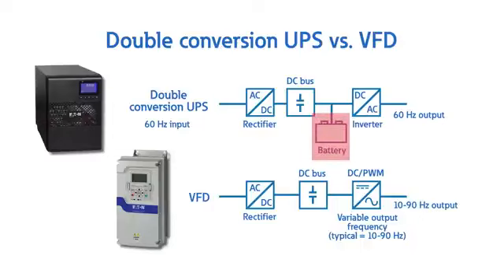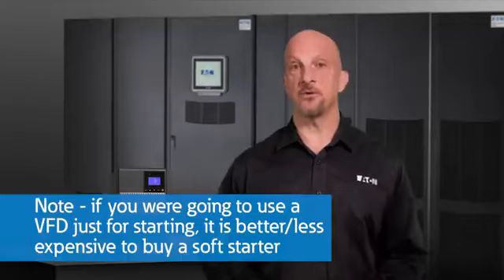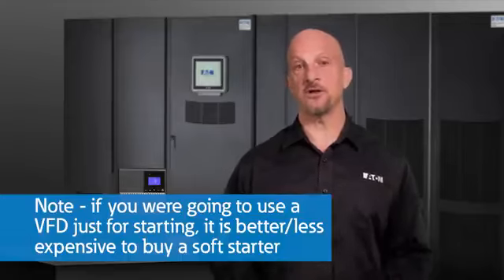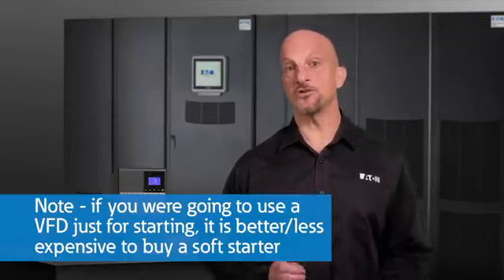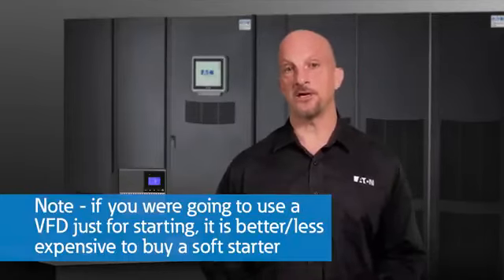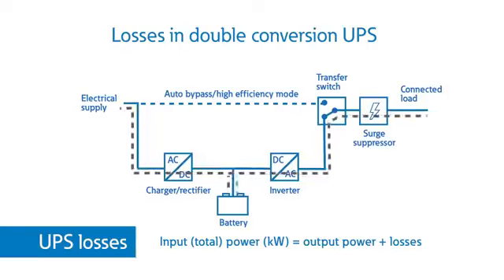The UPS also has a battery on the DC bus alongside the capacitor for outage protection, but the UPS always operates at 60 Hz in and 60 Hz out. The VFD adjusts the output frequency to control the motor speed during normal operation, as well as startup and shutdown. That's why we call them variable frequency or variable speed drives. You wouldn't buy a VFD just to start a motor and run at 60 Hz because the switching losses of the rectifier and inverter would cost you more money than running it across the line with the contactor. However, you do this with the UPS and forego the losses for the benefit of reliability.